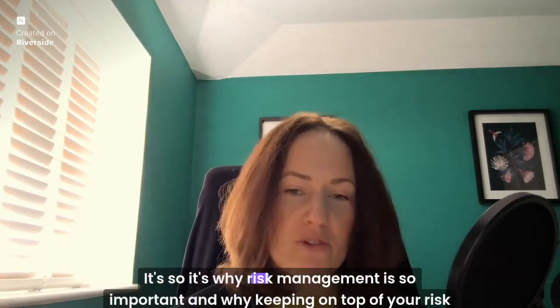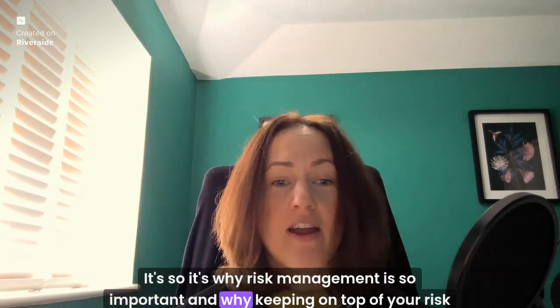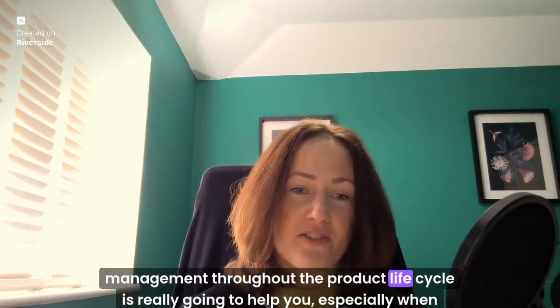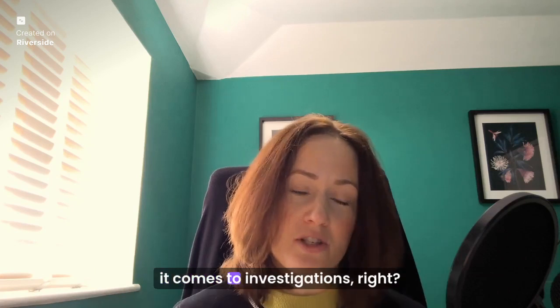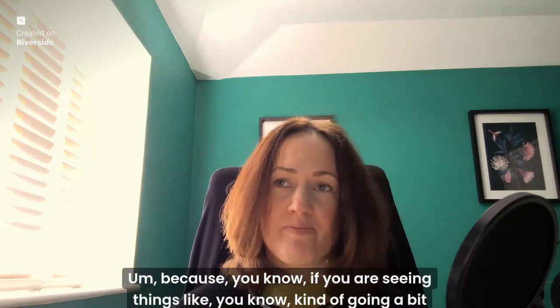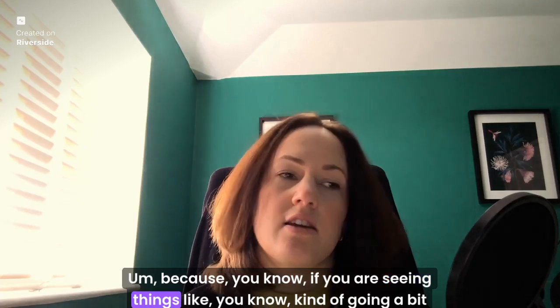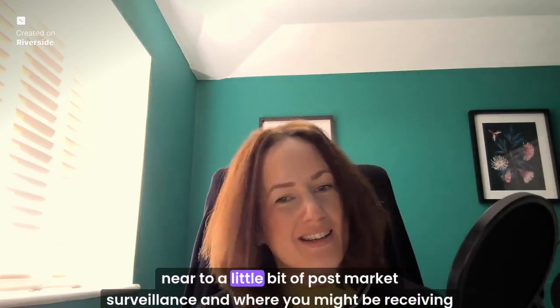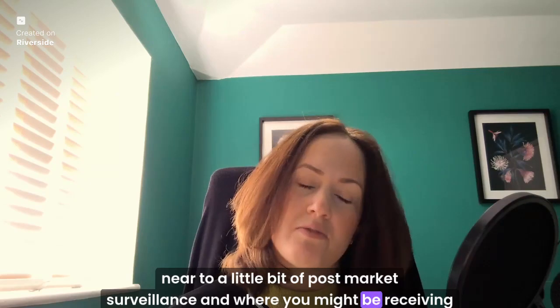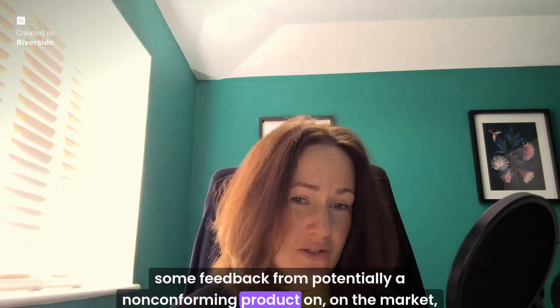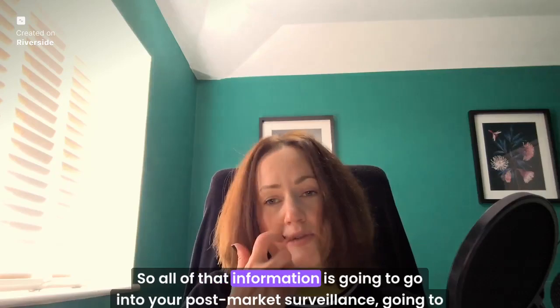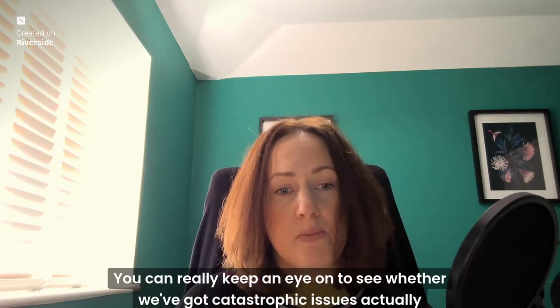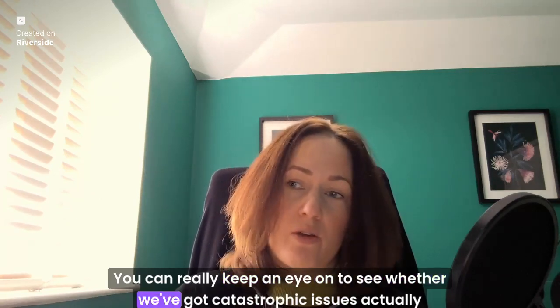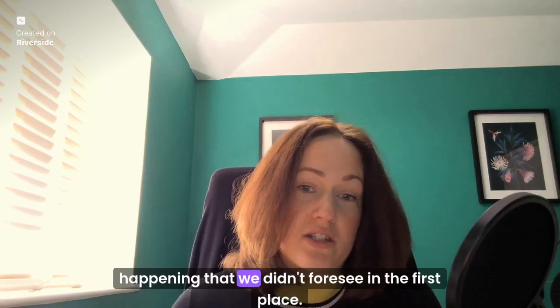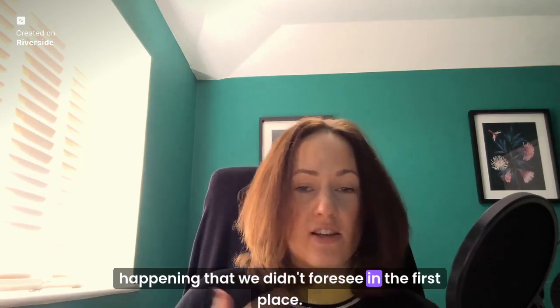It's such a good point. It's why risk management is so important, and why keeping on top of your risk management throughout the product life cycle is really going to help you, especially when it comes to investigations, right? Because if you are seeing things, going to a little bit of post-market surveillance, where you might be receiving some feedback from potentially a non-conforming product on the market, all of that information is going to go into your post-market surveillance and update your risk management, and you can really keep an eye on whether we've got catastrophic issues actually happening that we didn't foresee in the first place.